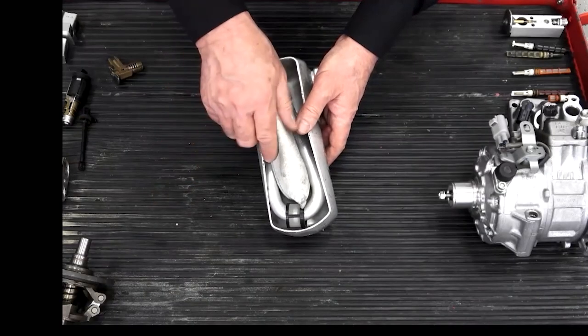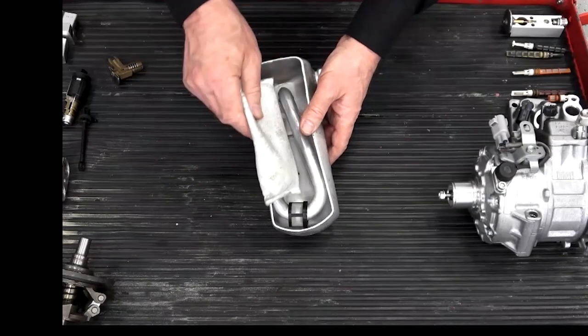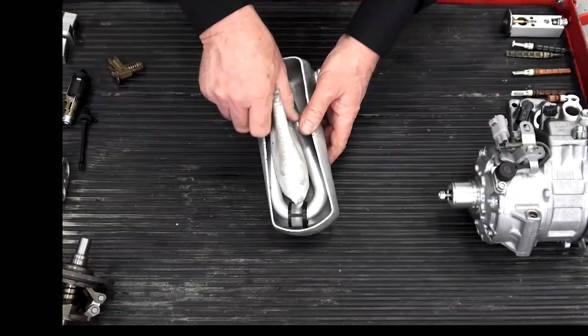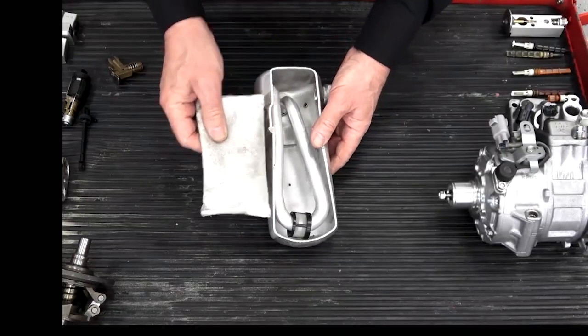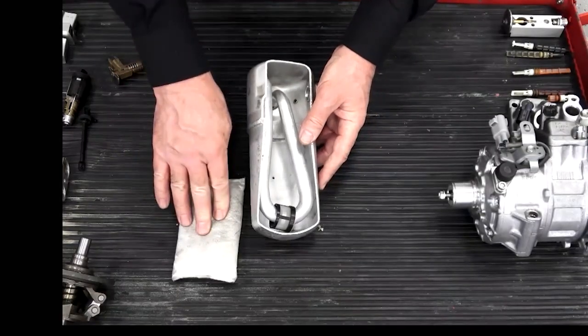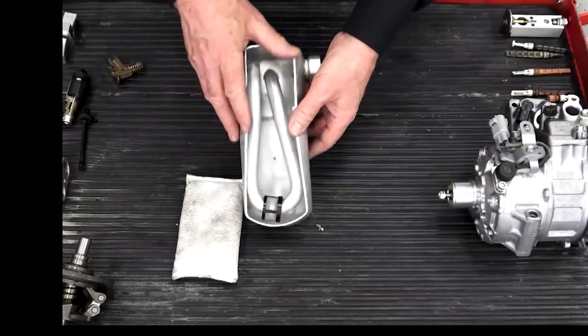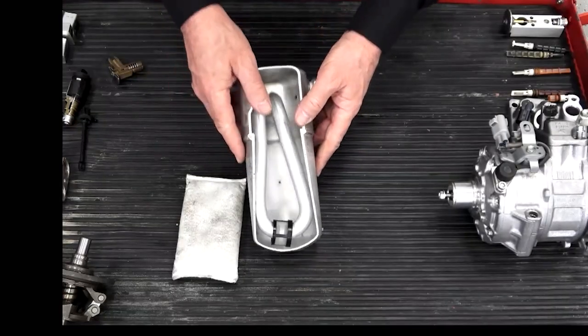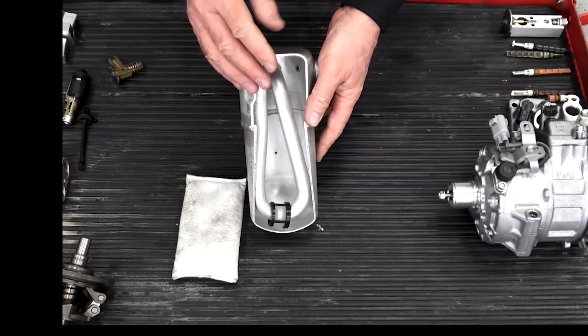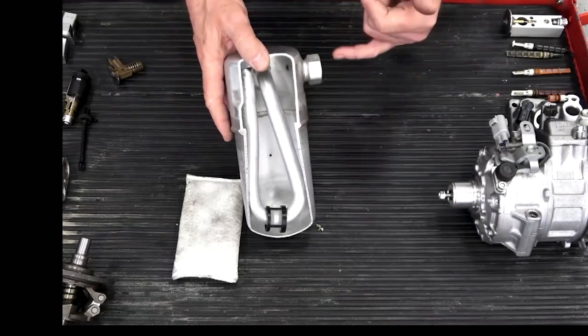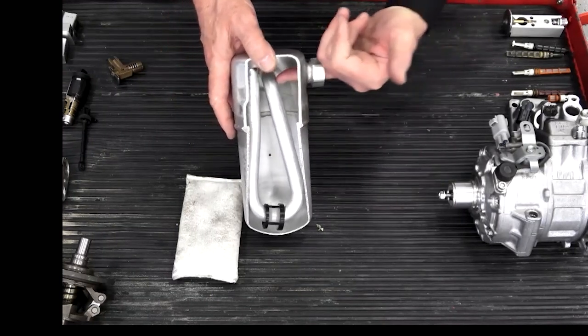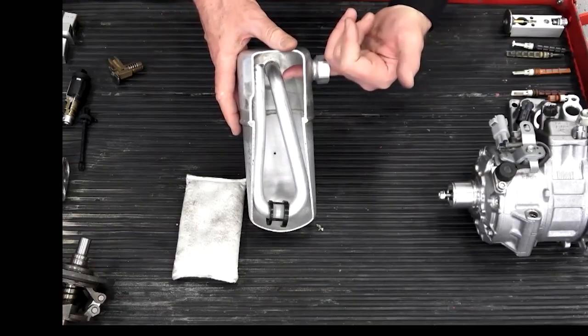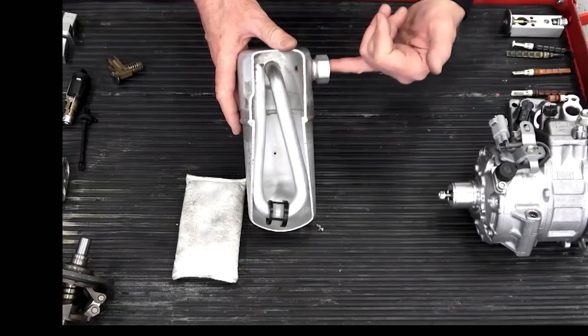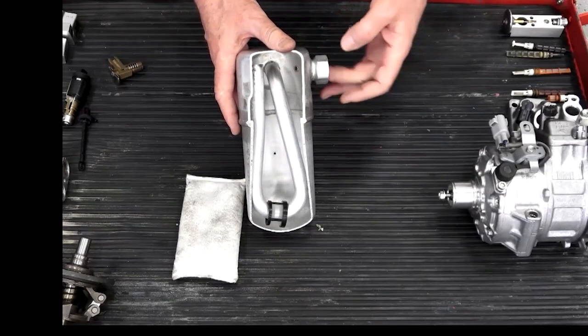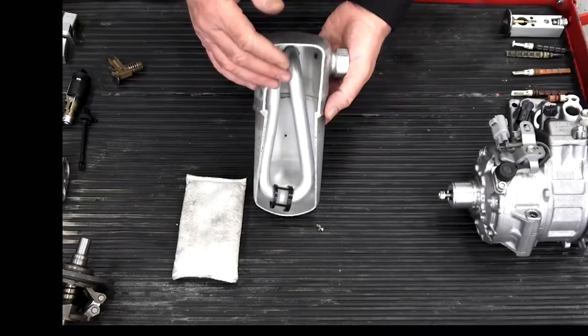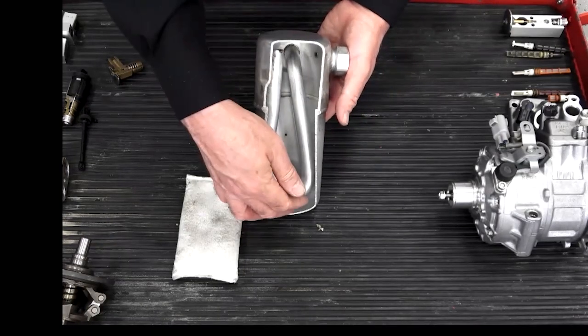I've seen them missing. We've cut cheap ones apart over the years. I often see them missing or some rogue flower or something inside of them. So that's storage, desiccant medium to absorb trace moisture. But the most fundamental function of the accumulator is that it is a liquid vapor separator. Remember, the refrigerant coming in from the evaporator is going to come in here. And remember I said on an accumulator system, it's going to be 95% gas with a little bit of liquid, right? So of course the liquid is going to drop down to the bottom of the can.